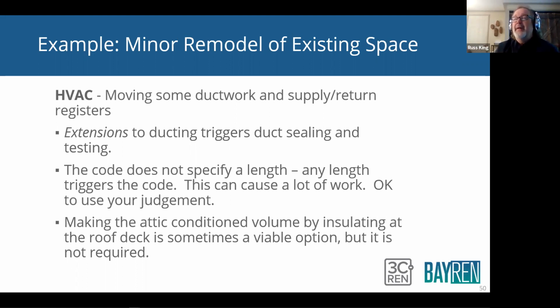And so I guess what I'm getting at is there's a lot of things you can do to kind of get around having to do it. And one of the things you can do is move the insulation from the T-bar ceiling up to the roof level. Now your ducts are inside conditioned space and you don't have to test them. So that's an option as well, okay? But extending any length of duct, even 1 inch, if you add 1 inch of duct to the length, technically that triggers the code, but you're allowed to use common sense as well, okay?